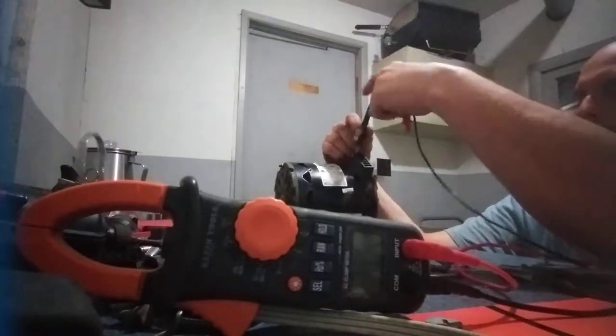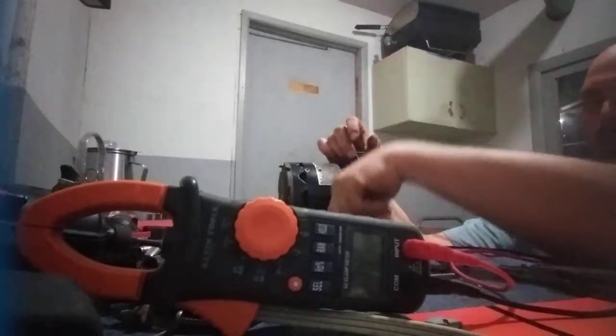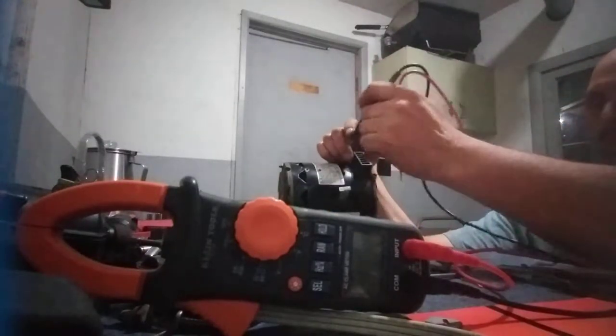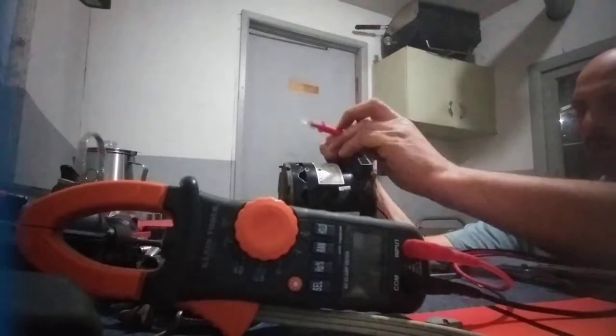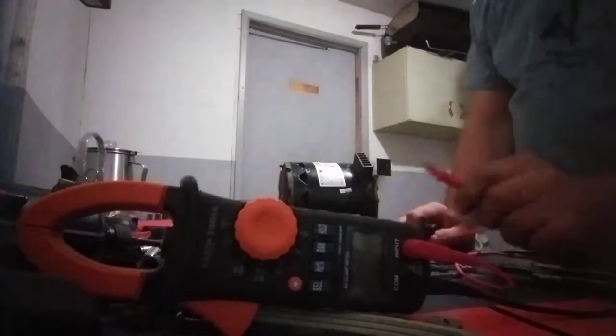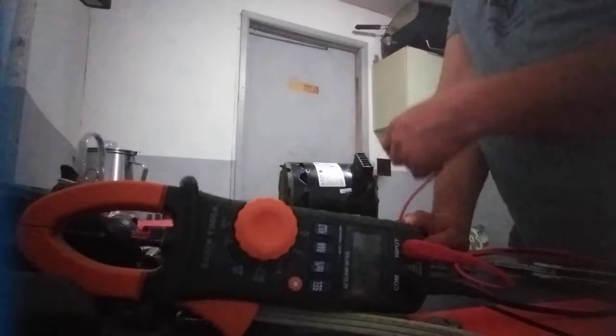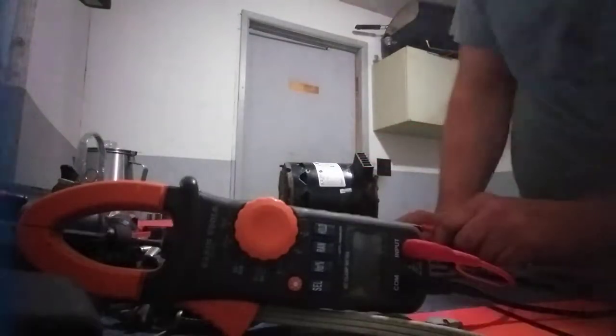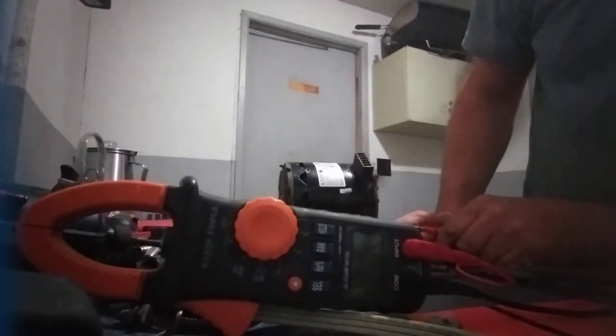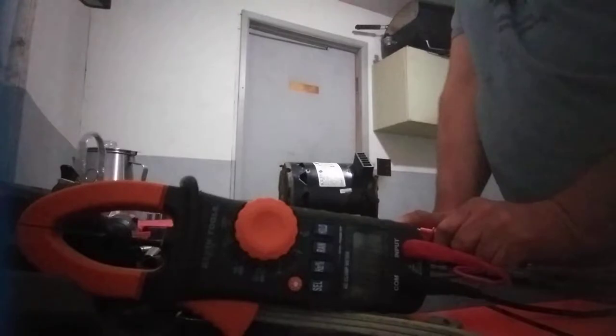That tells you the contacts are okay. If you get OL, that means one of the contacts is burnt out and it's not working. If you get a straight 0.0, that means something is shorting out.